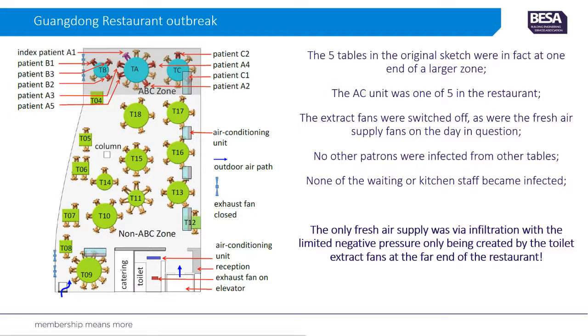And when we saw the full floor plan for that restaurant, it actually showed that it was a catalogue of errors in that restaurant that led to a stagnation of air in a particular zone, and a revelation that the extract fans weren't even working. So on the left hand side you can see 4 extract fans, 2 at the top and 2 at the bottom, and it transpired they weren't even actually operational at the time. The only makeup air that was coming into that building was through the lift shaft. So every time somebody came up or down in the lift, at the bottom right corner, there was a bit of air infiltration through the lift, and there was an extract only by the 100mm exhaust fan in the toilets at the bottom of the screen.